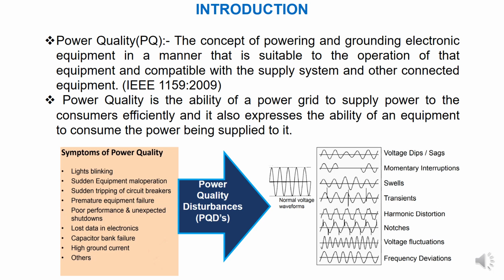There are some power quality issues, like light blinking, sudden equipment maloperation, sudden tripping of circuit breakers, premature equipment failure, poor performance and unexpected shutdowns, lost data in electronics, capacitor bank failure, high ground current, and others. These symptoms of power quality issues are due to some power quality disturbances.